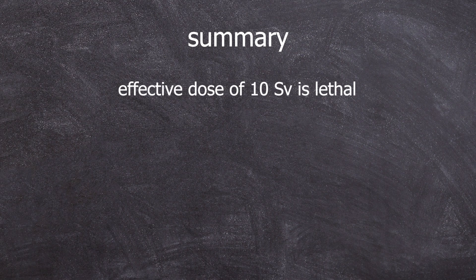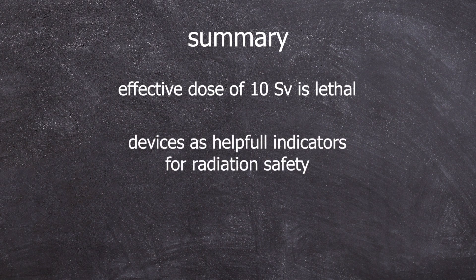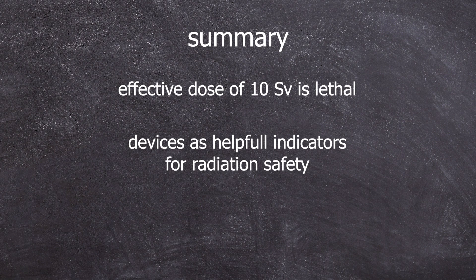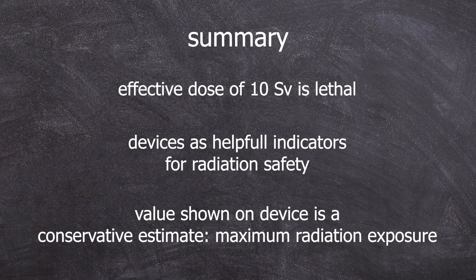As a conclusion, the dose rate always has to be a conservative estimate. What's displayed on the device is the maximum dose a body could receive. Now we can understand the thoughts behind an effective dose and an effective dose of 10 sievert is lethal. Such devices are helpful indicators for estimating the risk of radiation exposure, but calibration is usually very complicated and transferring all the factors behind this effective dose from the measurement that the detector took is very complicated. However, the measurements on the device should always indicate the maximum radiation exposure.